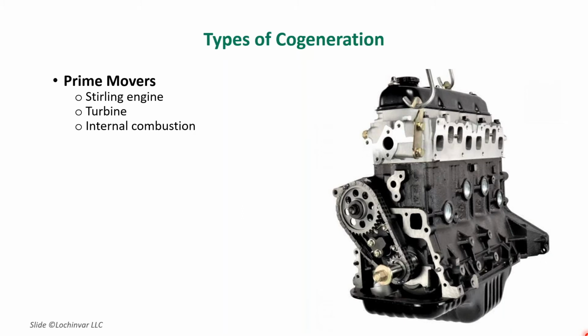In micro-cogeneration, most systems out there, including ours, need minimal maintenance. In our case, it's simply an oil change, air filter, spark plugs, a couple of sensors, and some hoses that have to be changed out, which can be done in 2 to 3 hours. Very simple process, about every 4,000 to 6,000 hours.